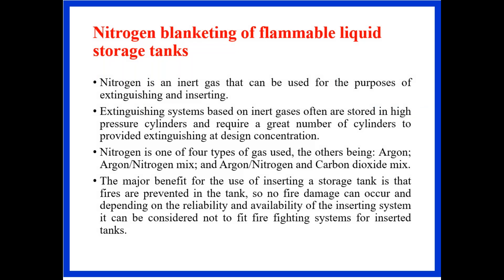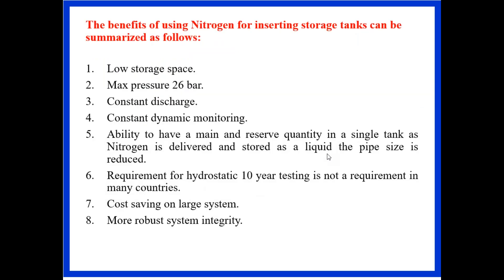The benefits of nitrogen blanketing include: low storage space requirement, maximum pressure of 26 bar, constant discharge, constant dynamic monitoring, ability to maintain main and reserve quantities in a single tank, reduced pipe size since nitrogen is delivered and stored as a liquid, no requirement for hydrostatic 10-year testing, cost savings on large systems, and more robust system integrity.